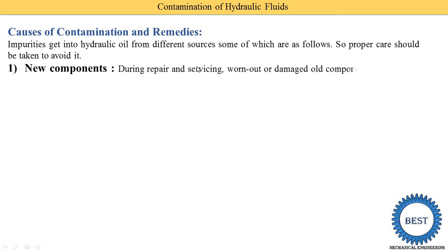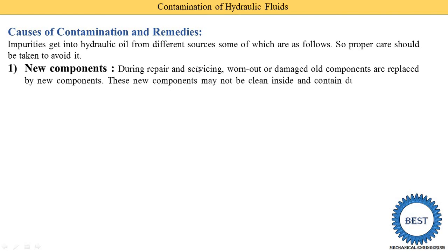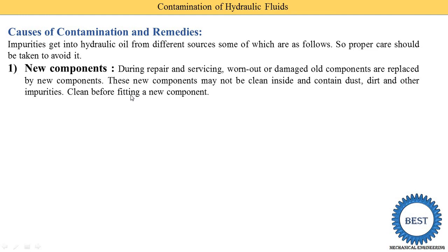The first cause is new components. During repair and servicing of a hydraulic system, worn out or damaged components are replaced with new ones. However, new components may not be clean inside and can contain dust, dirt, and other impurities. Therefore, new components must be thoroughly cleaned from the inside before being fitted into the hydraulic system.